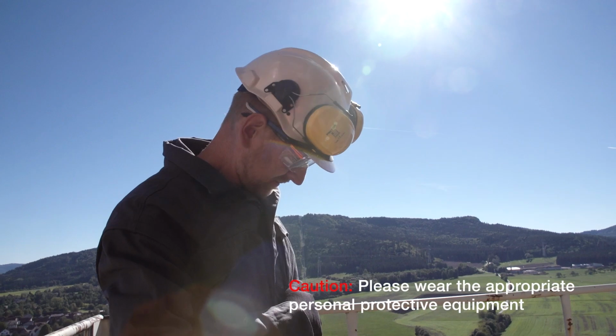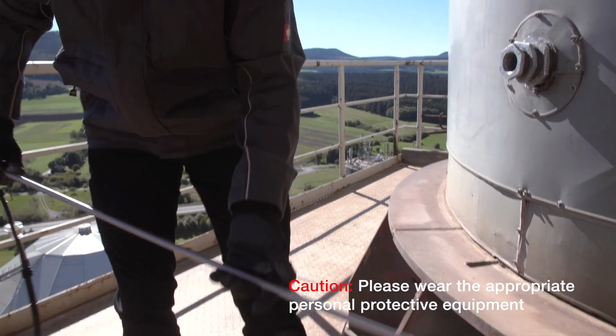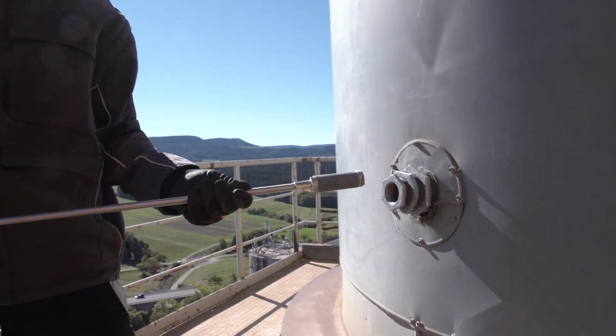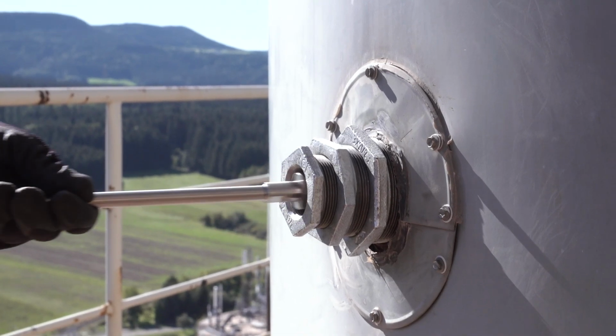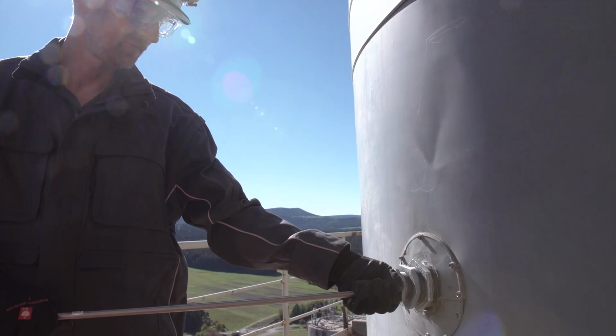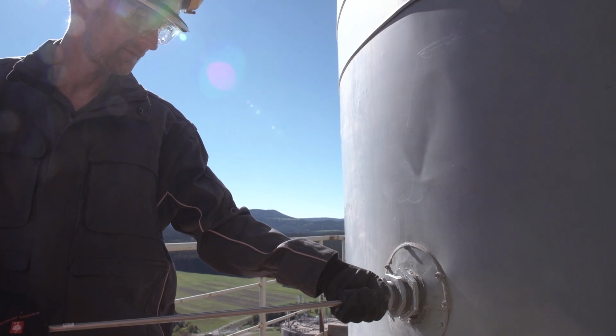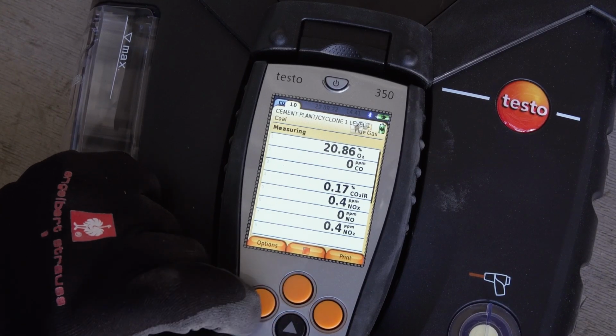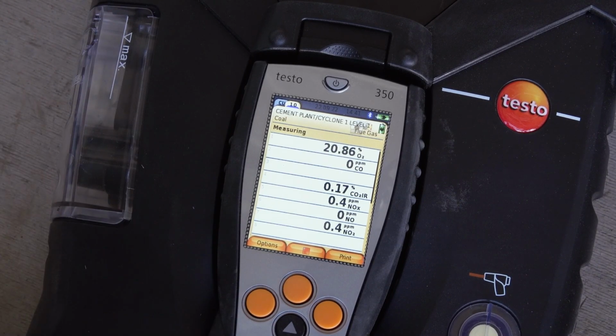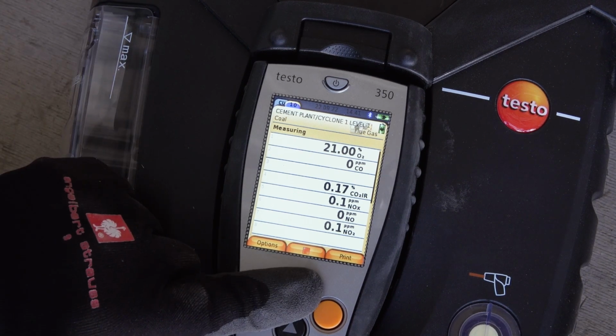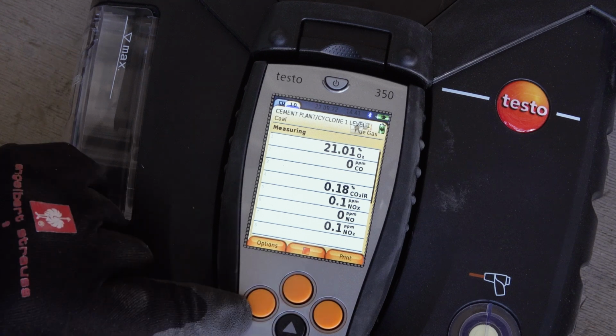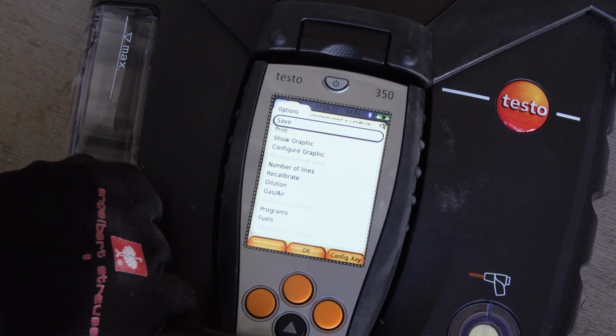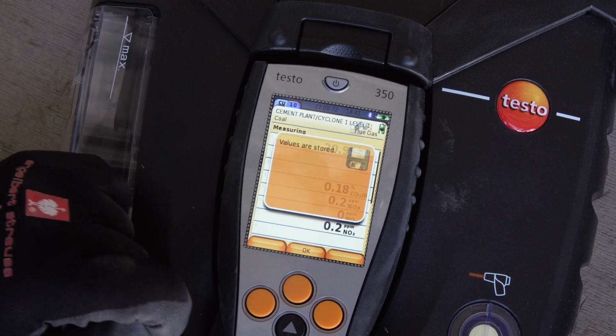The industrial probe with pre-filter is used for this measurement. This is connected directly to the exhaust duct of the plant. The probe tip should be in the center of the flue. Now the exhaust gas measurement can be started by pressing the middle button, green arrow. The measurement is ended by pressing the center button again. Via the menu item option/save, the measurement is saved under the previously selected folder.